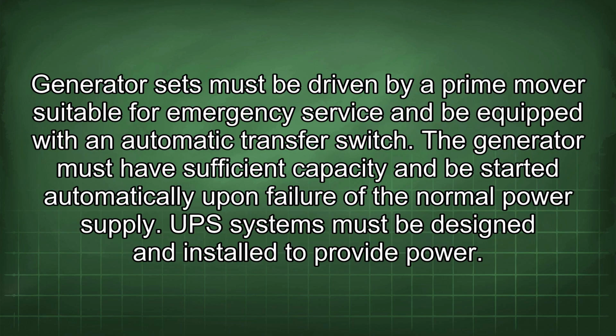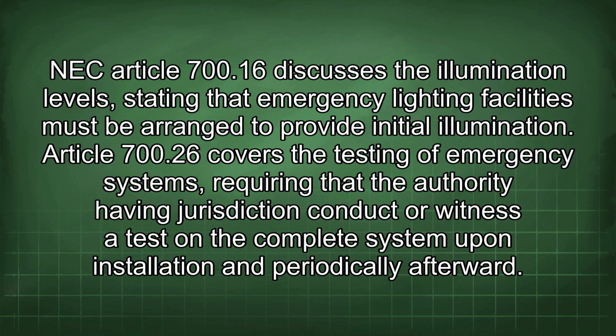Generator sets must be driven by a prime mover suitable for emergency service and be equipped with an automatic transfer switch. The generator must have sufficient capacity and be started automatically upon failure of the normal power supply. UPS systems must be designed and installed to provide power. NEC Article 700.16 discusses the illumination levels, stating that emergency lighting facilities must be arranged to provide initial illumination.